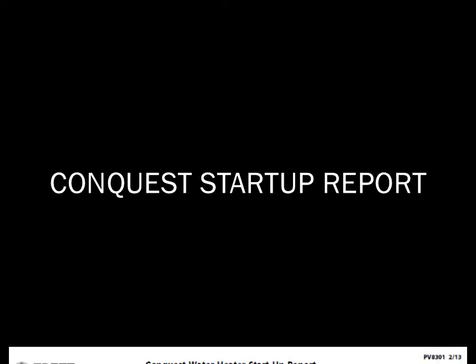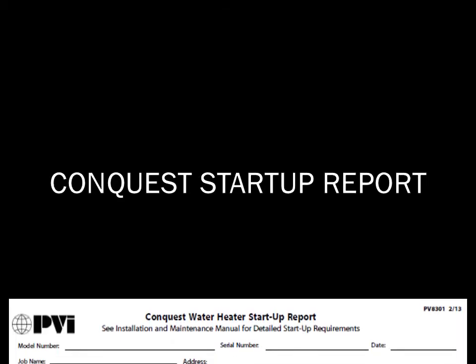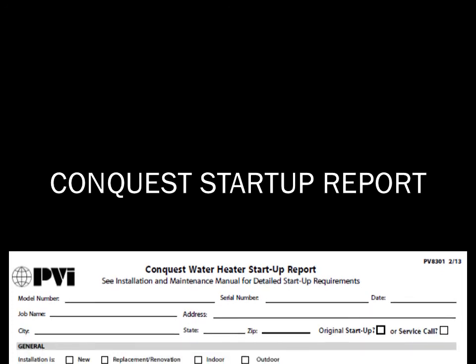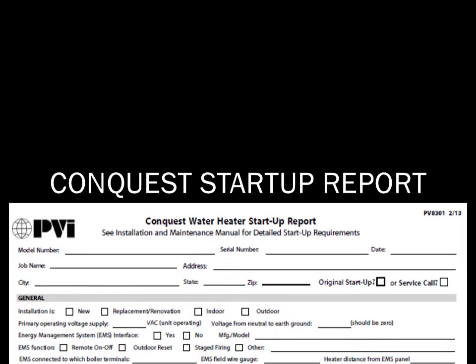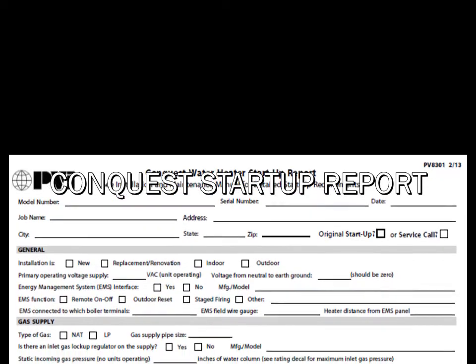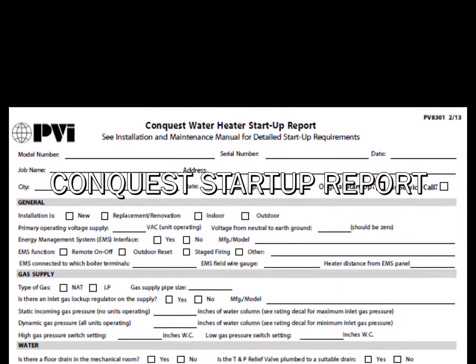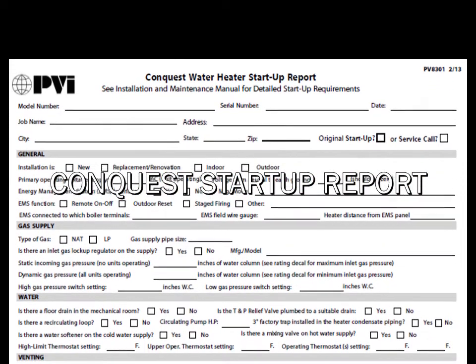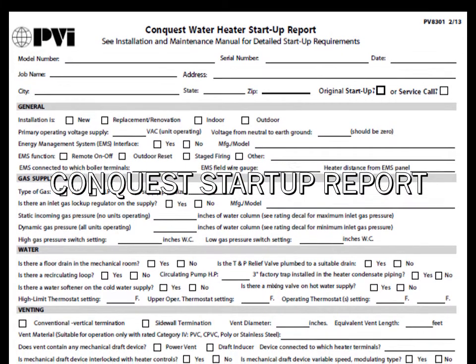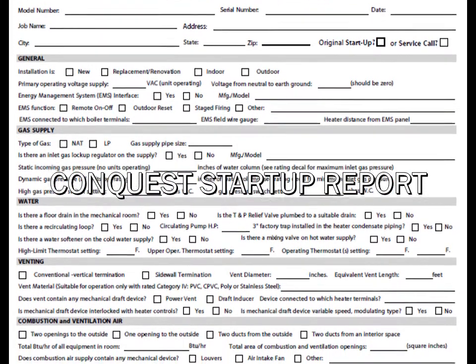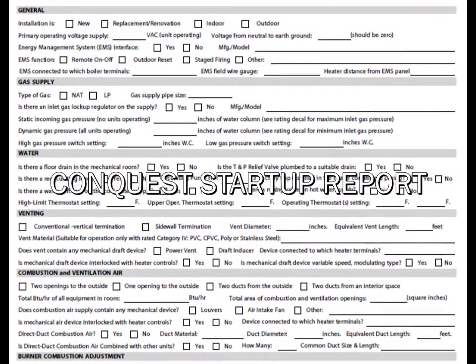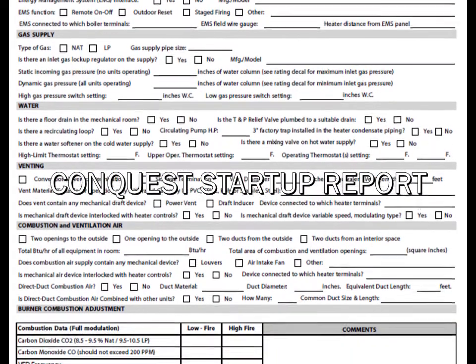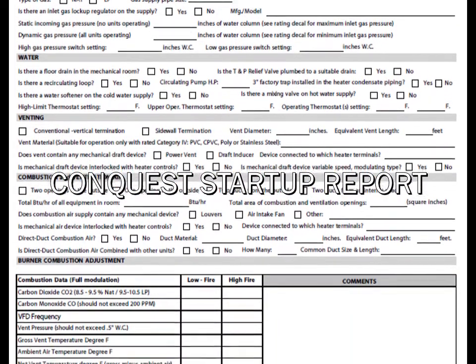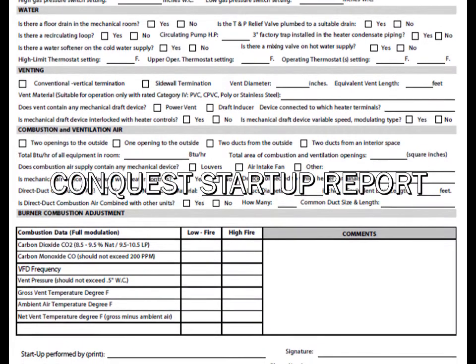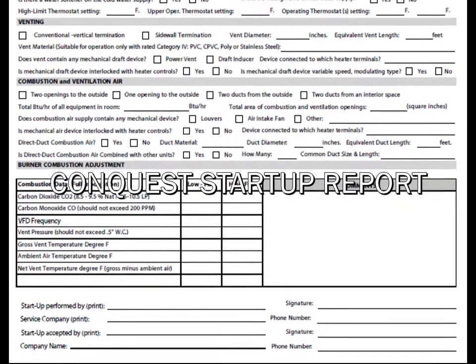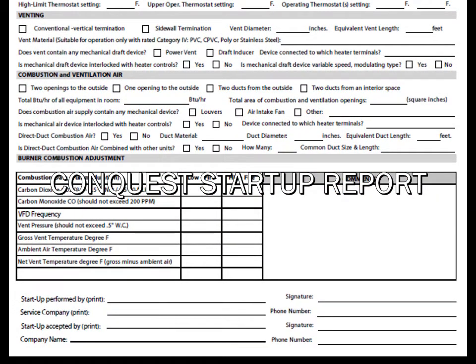The startup report furnished with this water heater must be completed and sent to the manufacturer to register the installation address and the start date of the product warranty. The information on the startup report is required. All voltages, fuel, pressure, temperature, and combustion parameters must conform to the manufacturer's specifications. Failure to ensure and document that the equipment is operating in a safe and reliable manner may cause property damage, personal injury, or death.